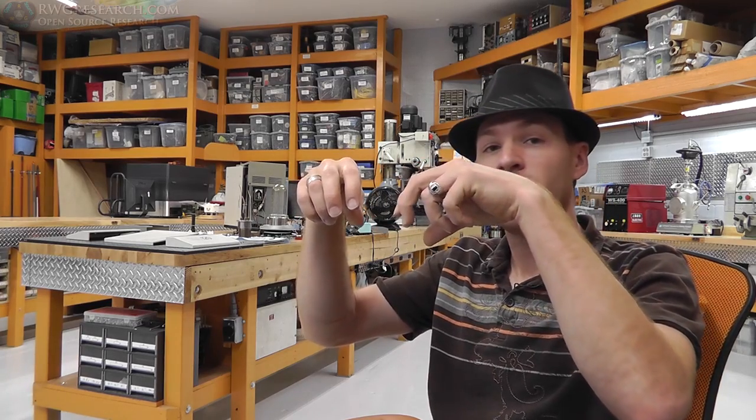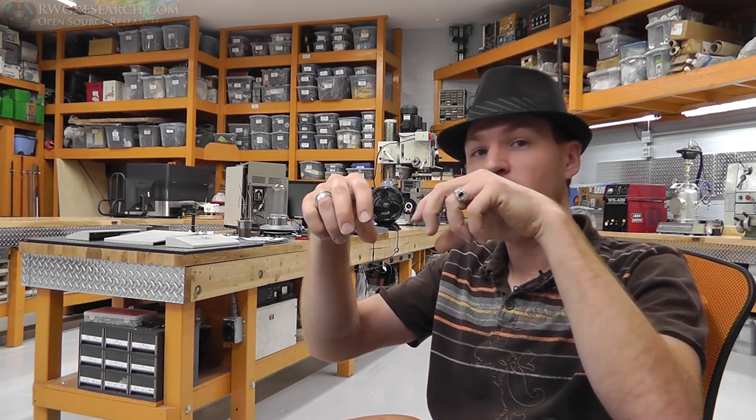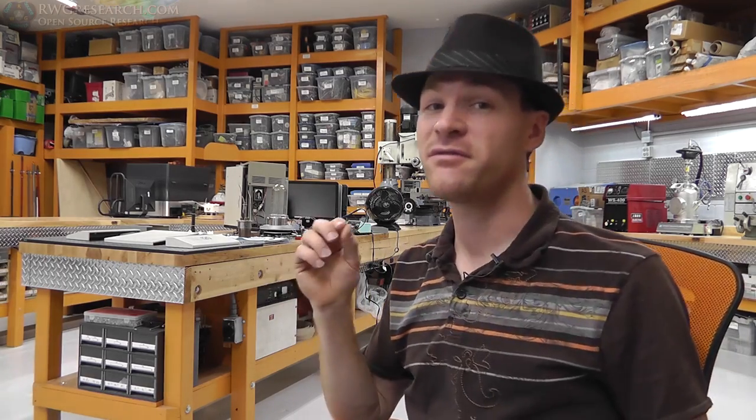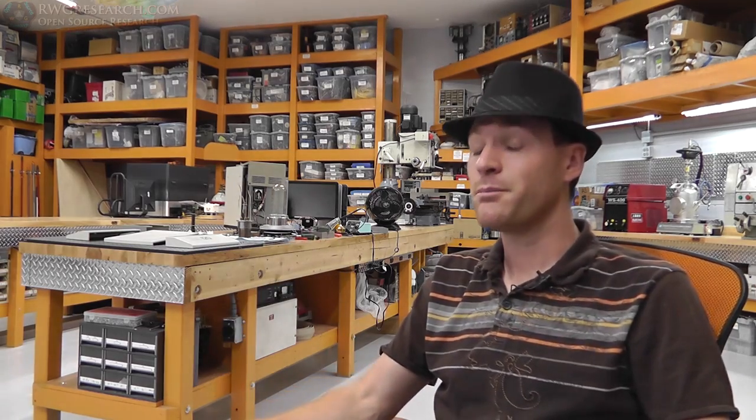What this device does is it takes a sample and a control and it measures the heat difference between the two and it can record that. It can record very small measurements down to the very low milliwatt into the microwatt range. Pretty cool stuff.